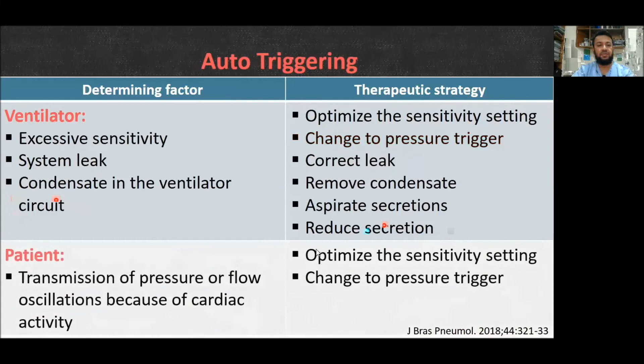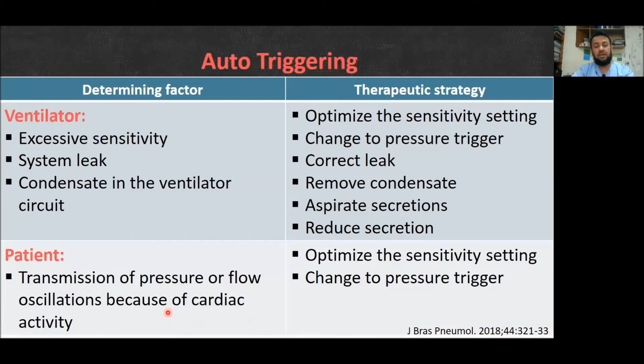So that can cause auto trigger. Or if there is leak in the circuit or water in the circuit, then it can cause auto trigger. So we have to optimize the trigger setting. We can change to pressure trigger rather than volume trigger. That can help to prevent auto trigger. If there is circuit leak, that has to be checked, circuit water has to be removed, and too much secretion has to be removed. And other thing is patient's cardiac oscillation may be falsely detected by ventilator.